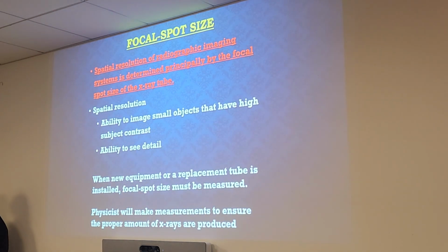So focal spot size helps with your spatial resolution. So it's the ability for small objects to have high subject contrast and for your ability to see more detail on your image. So anytime you get new equipment or if your X-ray tube is replaced, you must install the new focal spot, and the medical physicist must come in to measure that focal spot. All right. So there's 3 tools that the medical physicist will use to measure focal spot size. One is the pinhole camera. All you need to know is that it's difficult to use and it uses an excessive amount of X-ray exposure, because they've got to get a certain amount of photons to actually reach through that tiny hole.